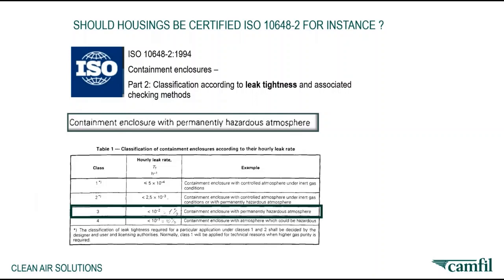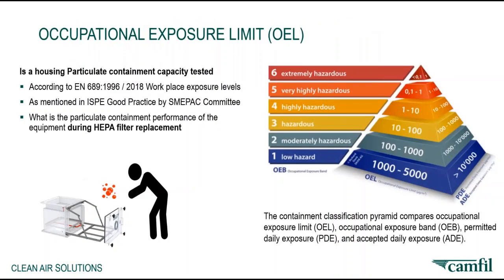As we said previously, we all know individual test reports are mandatory for HEPA filters from H13. But what about housings? Are test reports available? Other standards: we need to ask ourselves if housings can be certified to ISO 10648 in terms of leak tightness. If we look closely at the standard, we can say that yes, this should be included. So don't forget to check and ask your supplier for this one.